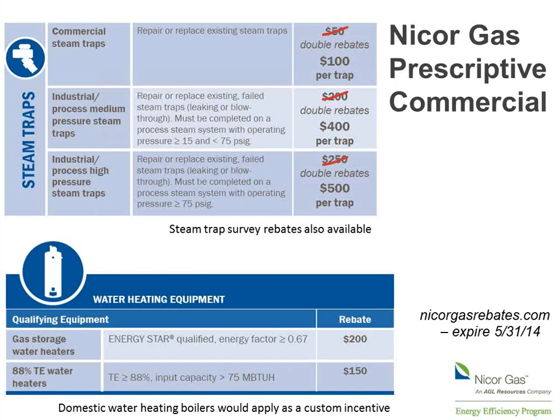They do also offer a rebate for doing a steam trap survey. So you basically have to have a company or even yourself, I suppose, come out and do a survey of all the traps in the building to see which ones have failed, and then you have to fix a certain percentage of those the first year, and you're eligible for X dollars per trap surveyed plus X dollars per trap fixed or replaced. So it's a pretty good deal. And the idea there is that you don't know if something's broken until you go investigate it.